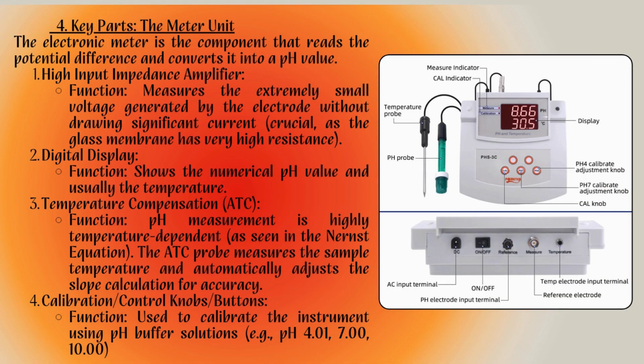The electronic meter unit is the brain of the operation. It has four critical functions. First, the high input impedance amplifier. The voltage generated by the electrode is extremely small and the glass membrane has very high resistance. This amplifier measures the tiny voltage without drawing any significant current, which is absolutely crucial for an accurate reading. Second, the digital display, which simply shows the resulting pH value and often the temperature.